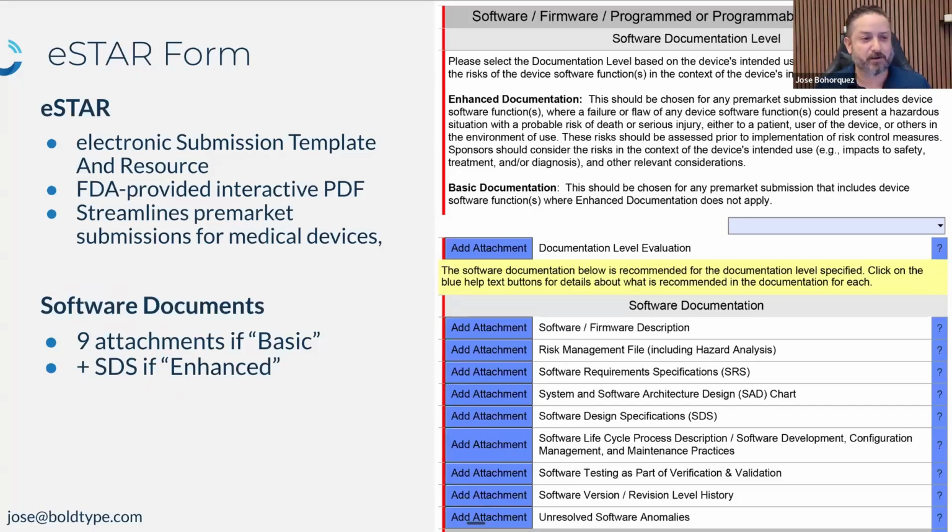And then maybe we can talk about, when your medical device has software, what does that mean from an eSTAR standpoint? Just so people know some of the basics, it's a PDF form. It's a protected PDF form that you cannot manipulate and change the way it works. You have to have Adobe Acrobat Pro to make it work. There are a couple other software tools that they try to make work with it, but they're always fixing the bugs because it doesn't work with those other ones well.